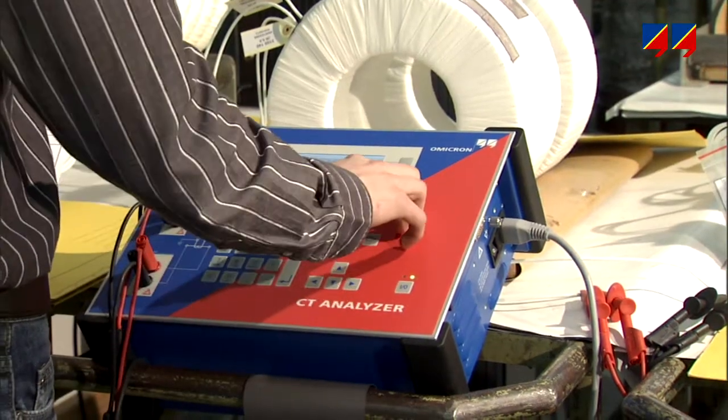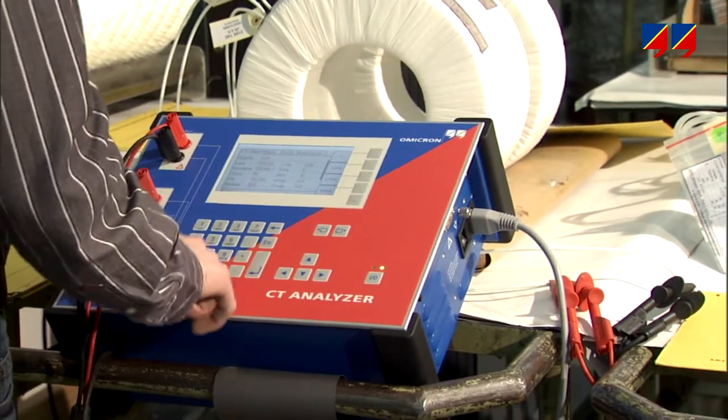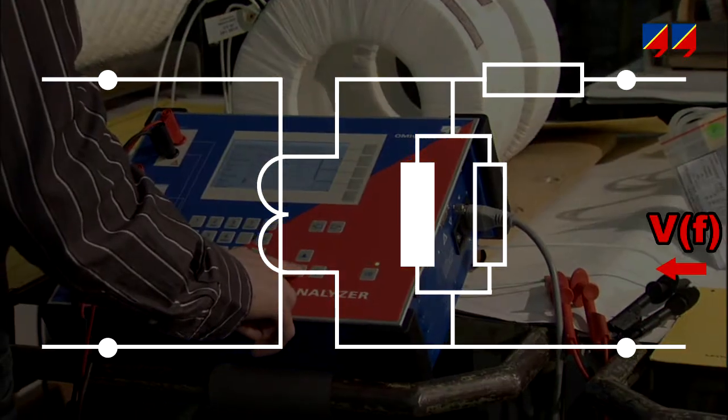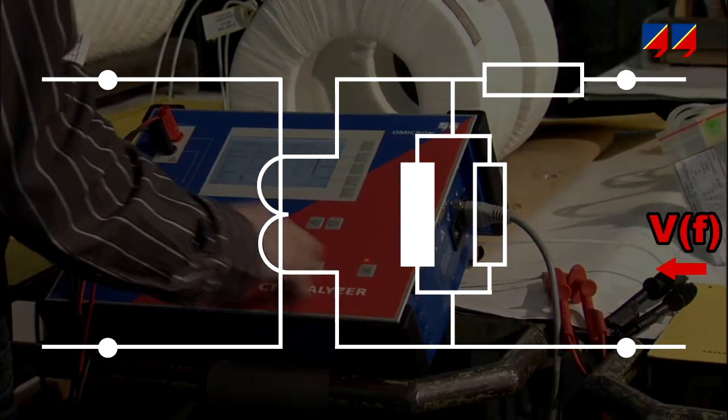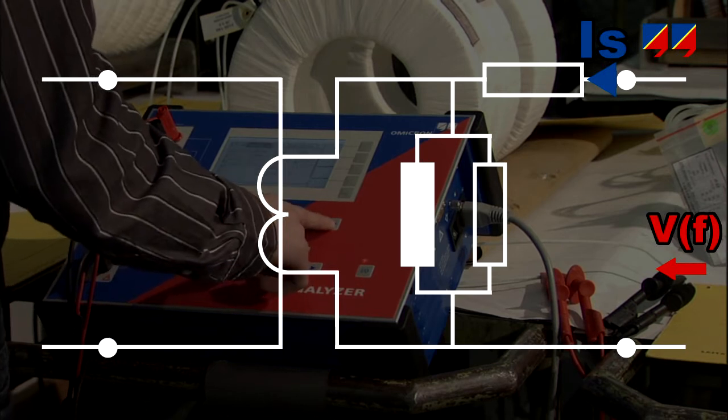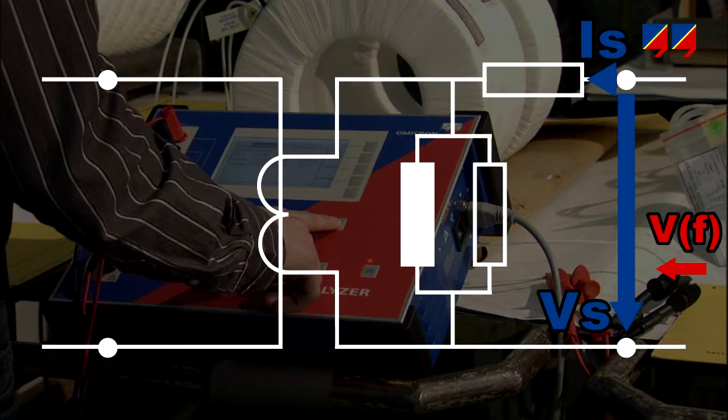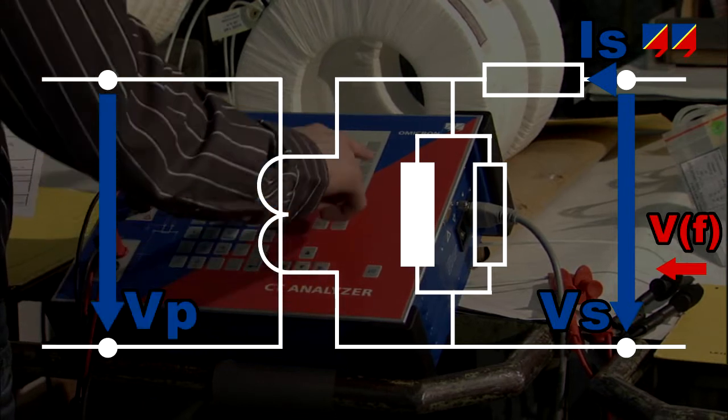CT analyzer determines all of the relevant parameters of a CT during a test run of typically one minute. It injects a variable frequency signal into the secondary side of the CT and measures the current injected into the secondary terminals and the corresponding voltage applied, as well as the voltage induced on the primary side.